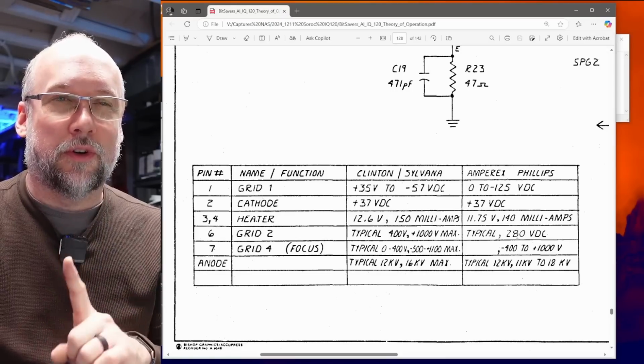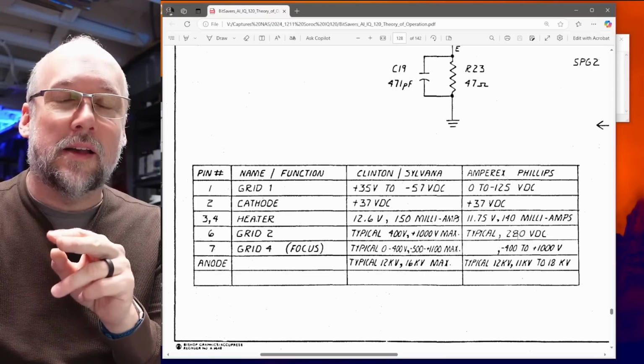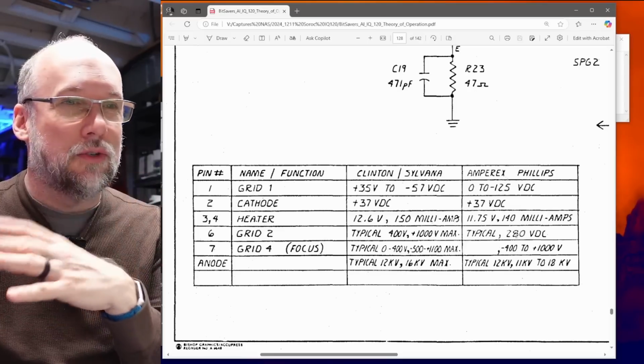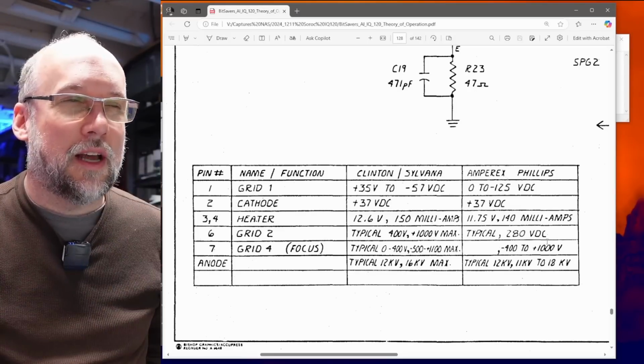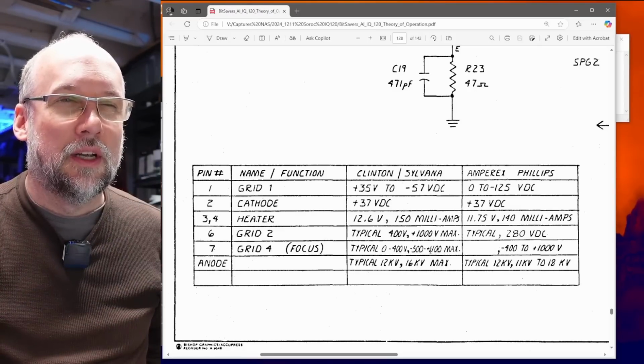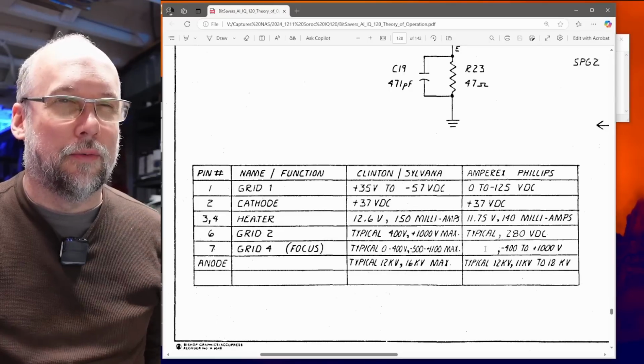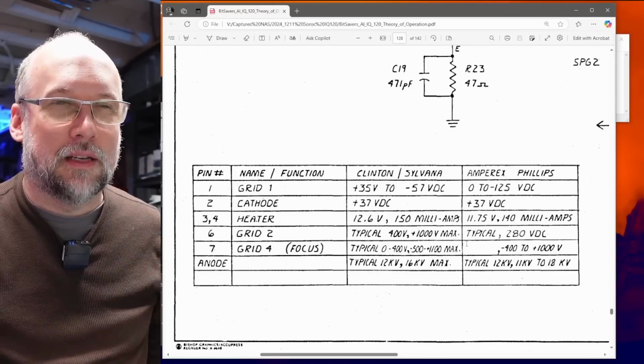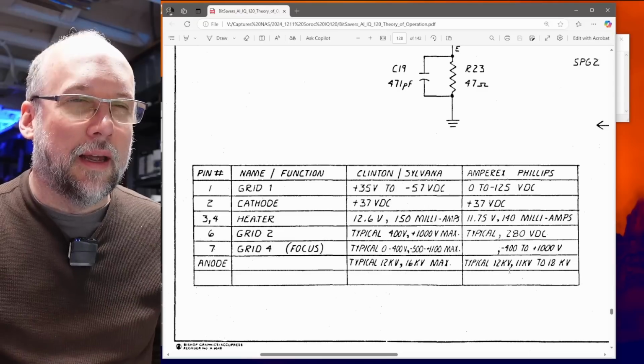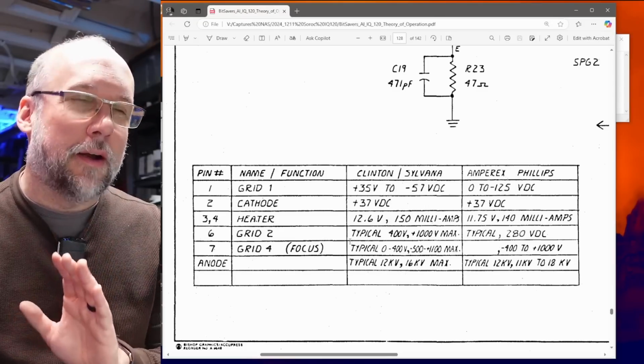It says typical 280 volts DC, and when I adjusted the pot it was around 220 to 270 volts, which coincides with this. Also the focus voltage, typically 0 to 400 volts — I have a feeling part of this is missing, but I wouldn't be surprised if it's also 0 to 400 volts, and 12 kilovolts on the anode, which is what we're getting on both of them.